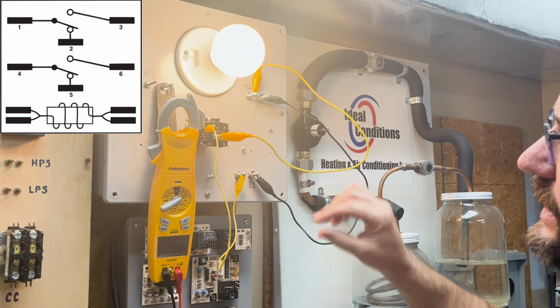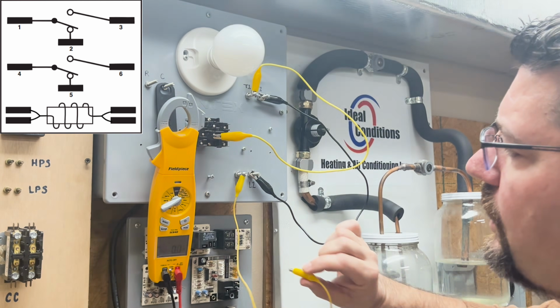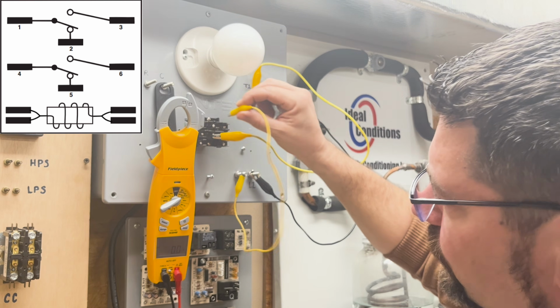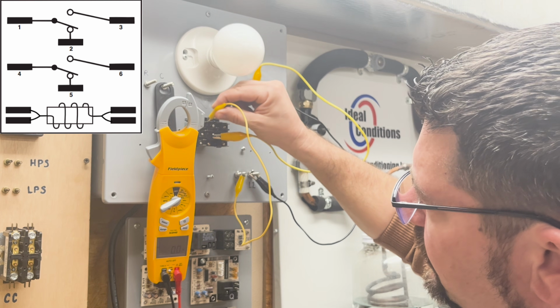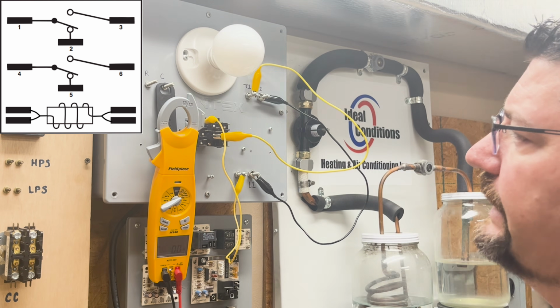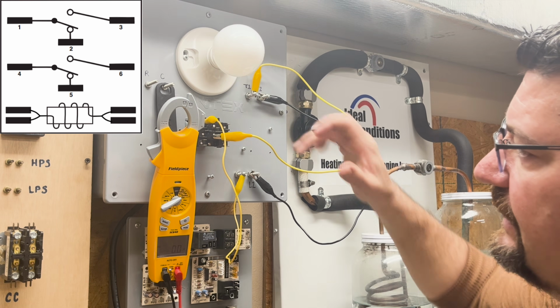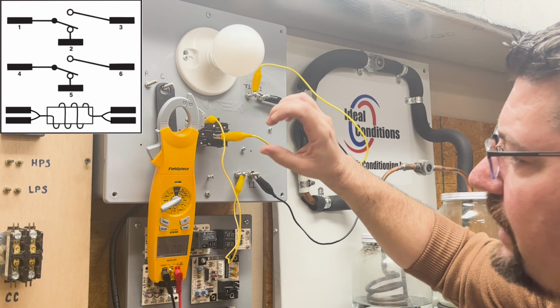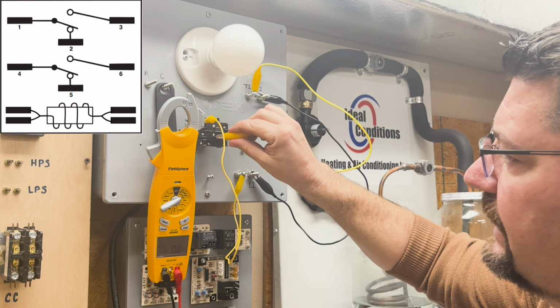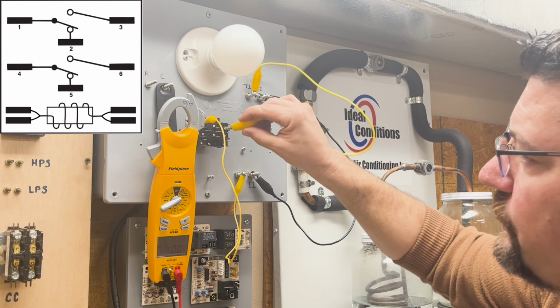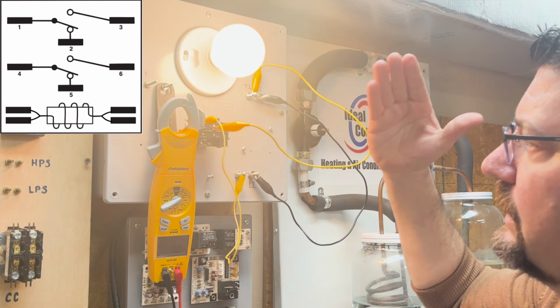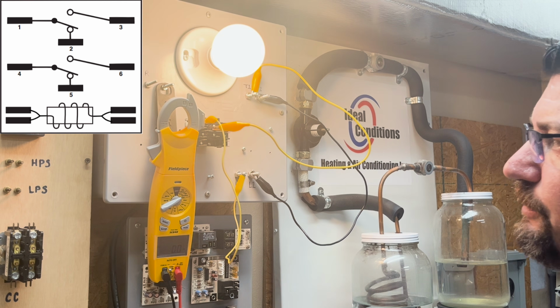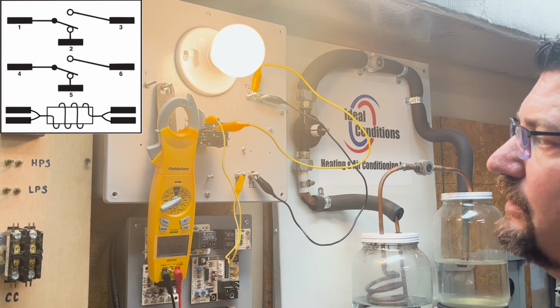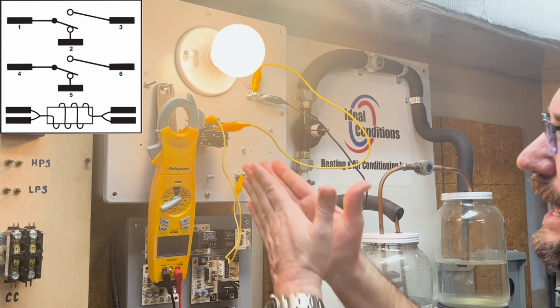The same thing, if I'd come up and I'd take power away from it and I put line voltage up here to terminal 1 on the relay, 2 is sitting there with this voltage present. All I have to do is connect my T1 terminal up to 2 and my light comes on. So this relay is pretty cool because I can get loads to energize without 24 volts.